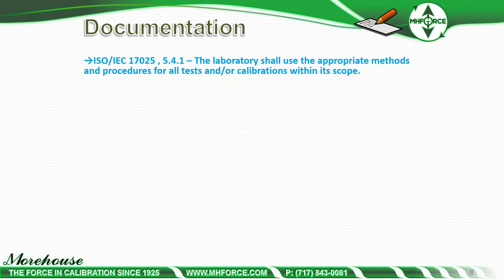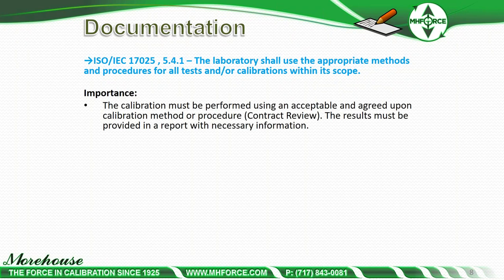A little overview on documentation: ISO 17025 section 5.4.1 states the laboratory shall use the appropriate methods and procedures for all tests and/or calibrations within its scope. The real importance is that calibration must be performed using an acceptable and agreed-upon calibration method or procedure. This is the contract review phase — we should have the email, the conversation, whatever the preference is. And the results must be provided in a report with the necessary information.